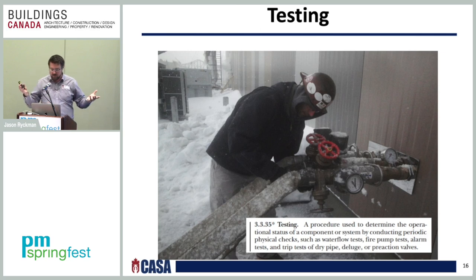Testing is basically a procedure to determine the operational status of a component or the system by conducting periodic physical checks, such as water flow tests, fire pump tests, alarm tests, trip tests on dry systems, deluge systems, or pre-action valves, and so forth. The test is a follow-up of the original acceptance test at intervals that are specified in the appropriate chapters within the NFPA 25 document.